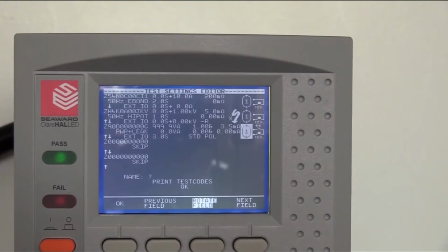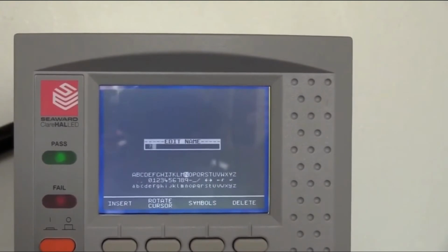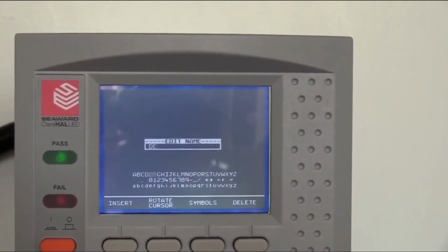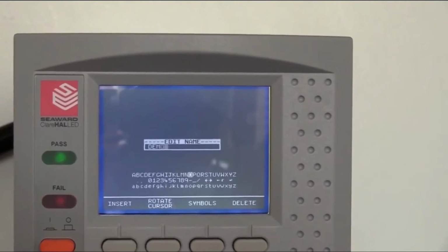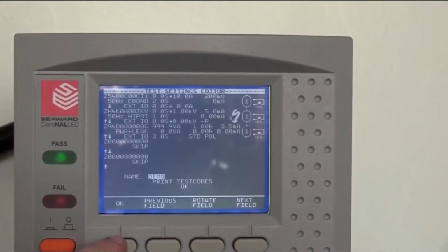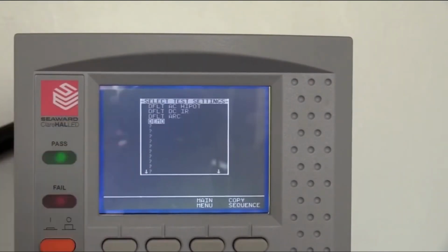Finally, again, we can set how many tests we want to perform, and again we can set a start condition. For all of our tests for today's example, we're going to set to start when I press the green button. So this is essentially now the test sequence created. The final step is to give the test a name. So we can scroll down to the name, press the green button, and this then allows us to edit a test name. For today, we'll just call it demo. Press the green button, press the OK key to confirm, and that test you can see now is in our test sequence list. Simply press the red button to come out. That test is now stored and it's ready for use.